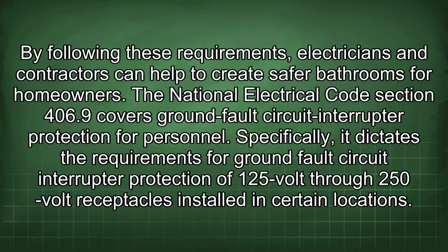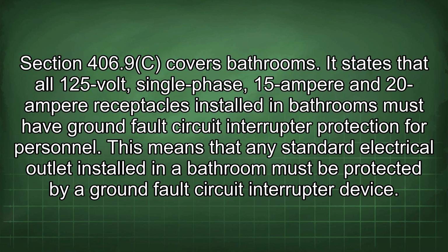The National Electrical Code Section 406.9 covers ground fault circuit interrupter protection for personnel. Specifically, it dictates the requirements for ground fault circuit interrupter protection of 125 volt through 250 volt receptacles installed in certain locations. Section 406.9c covers bathrooms. It states that all 125 volt, single-phase, 15 ampere and 20 ampere receptacles installed in bathrooms must have ground fault circuit interrupter protection for personnel.